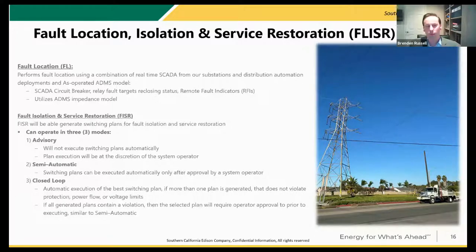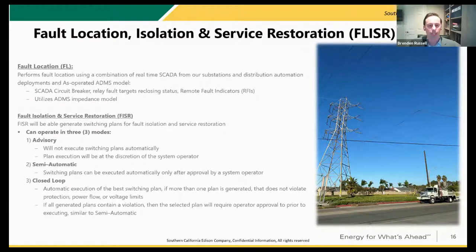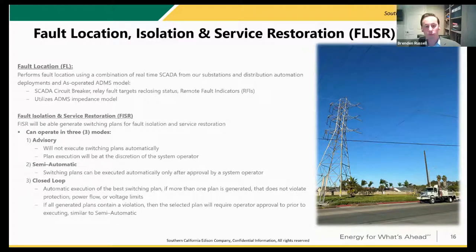We have a two-stage approach to roll this out. We plan to roll out the assisted switching functionality first — the semi-automated FLISR capability will provide a recommendation to the operator, and the operator will then make the final decision to execute that recommendation. Then the closed-loop FLISR is eventually where we want to get to, rolling this out across all our 4,500 circuits at Southern California Edison, where the system identifies the fault and automatically isolates and restores as much power as possible without any operator intervention.